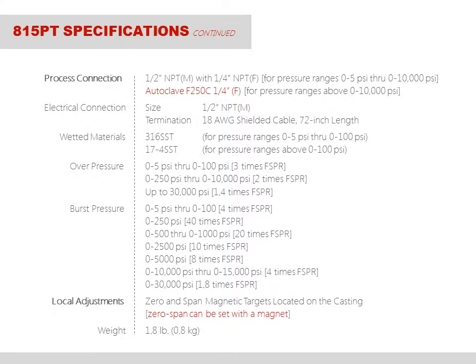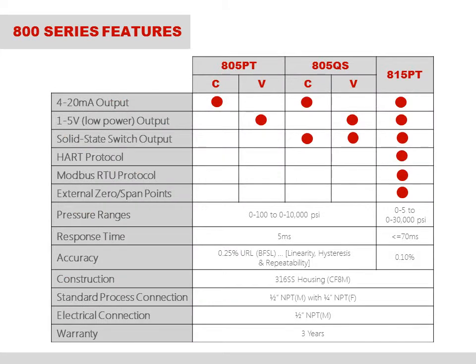Other important specifications are: the 815 comes standard with hermetically sealed 72-inch long color-coded flying leads. Even though the 815's housing is constructed of 316 stainless steel, it weighs only 1.8 pounds. Standard wetted materials are made of either 316 or 17-4 stainless steel, and to demonstrate the confidence that SOR has in the quality of our products, we back the 815 with a 3-year warranty.